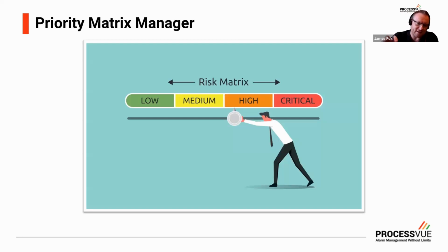And the idea is that the business will go through and it will review each alarm based on each category. What's this alarm's impact on the environment? It's minor. What's this alarm's impact on health and safety? Well, there's a major risk here, so we'll select it accordingly. And you go through the matrix. Now, the alarm priority methodology should be stored and available within your alarm philosophy document.